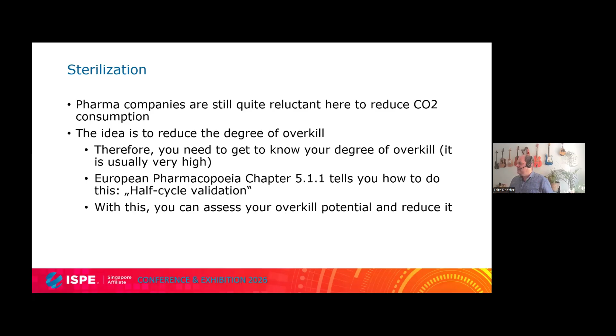So the pharmacopoeial chapter wants to get to know, the inspector wants to get to know your degree of overkill. How safe is the process? This is from a GMP perspective the idea behind this half cycle validation, but it's also good for energy saving. You can also get to know your process. How much overkill am I applying, and can I reduce it? Could I apply somewhat less steam here? Yes, you can, and this is the way to prove it and to validate it. It's in the pharmacopoeia, it's accepted, it's validated. This method, just do it.